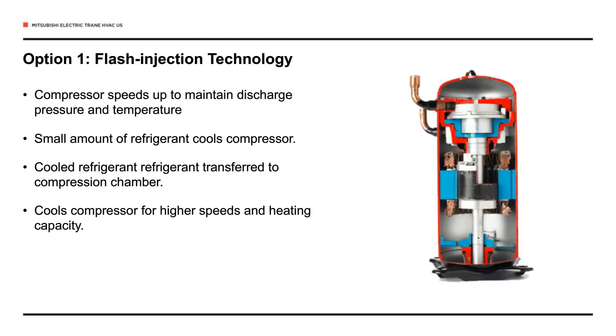Flash injection technology is offered by many manufacturers. Some manufacturers have a purpose-built piece of equipment for extremely cold weather climates, like Mitsubishi. Some integrate this, or a variation of flash technology, into their standard product. But the way it works is essentially, as it gets colder outside, we have to overspeed the compressor to capture more heat from colder ambient air. And there are limitations to how much we can overspeed that compressor.